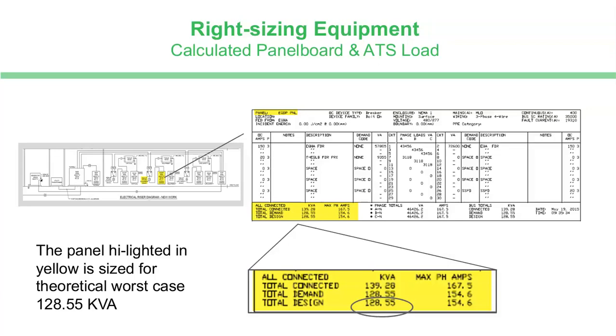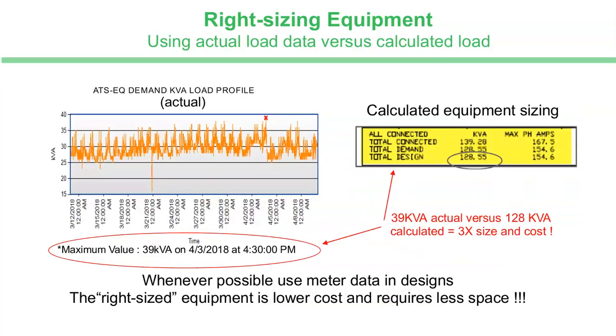In this example, you can see that the panel that the transfer switch is feeding is sized at 128.55 kVA. But when we look at the actual data, the maximum ever recorded on it was only 39 kVA. So what we're looking at here is the ability to avoid equipment that would be 3 times larger and 3 times more expensive than needed. There's an opportunity here to use the data to derive savings in your capital expenses.